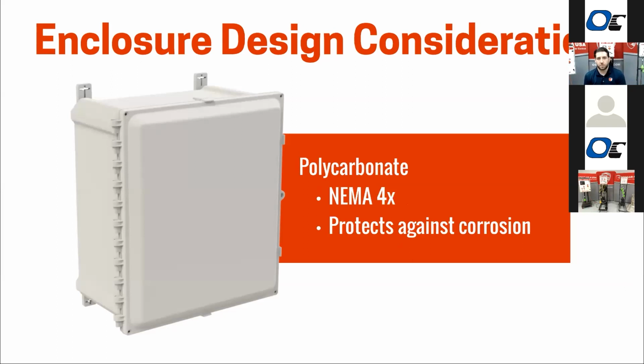Our standard for most of our panels is going to be this NEMA 4X polycarbonate type enclosure. I've had a lot of luck with these. It's a really good lightweight material, easy for the penetrations. The alternative a lot of times is fiberglass, which can be kind of a bear to deal with sometimes, so we've had a lot of good luck with the poly. It also carries a 6P or submersion rating before we start making any penetrations in it. So the smaller ones can be used as a junction box if you have to put it inside the pit.